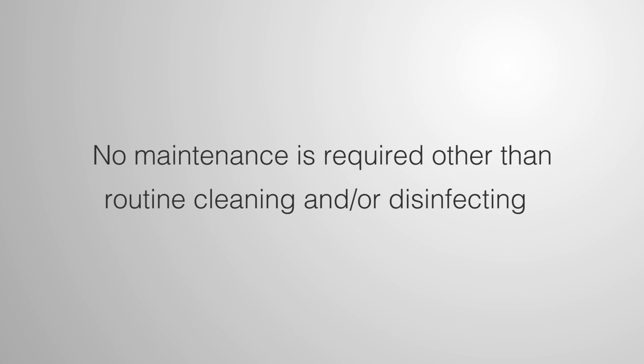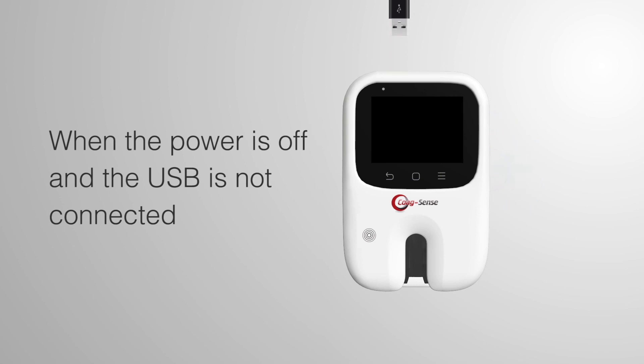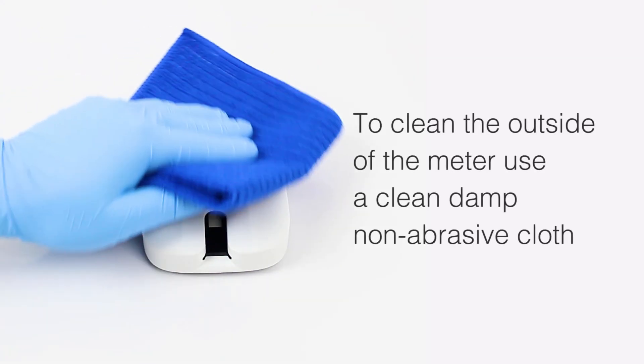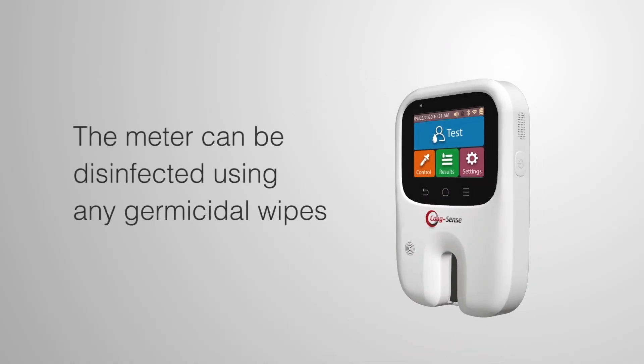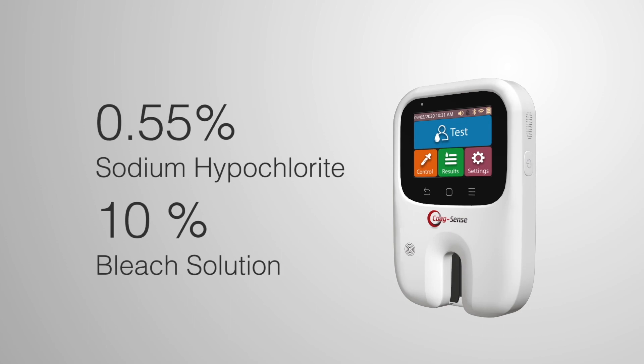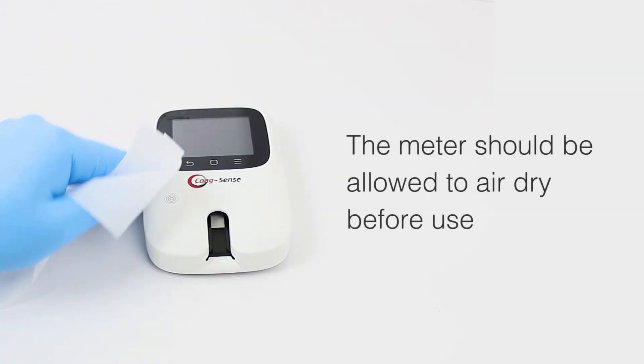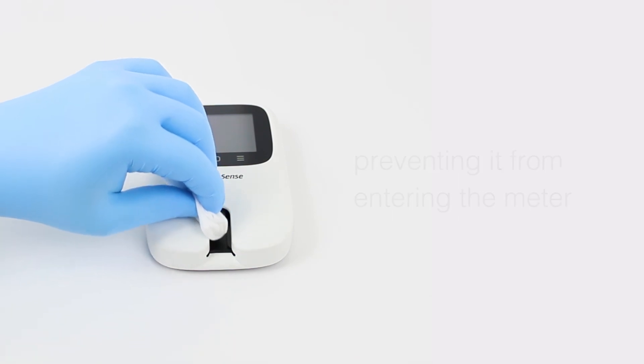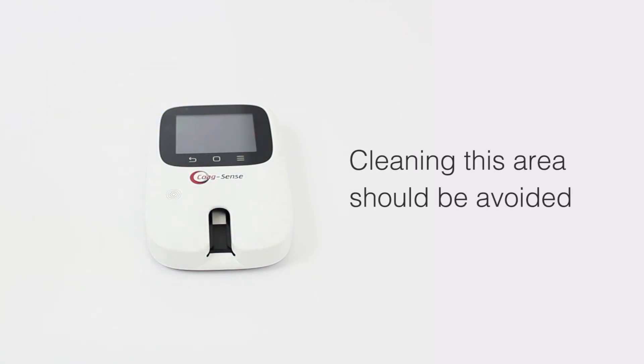No maintenance is required other than routine cleaning and/or disinfecting. When the power is off and the USB cable is not connected, the meter housing can be cleaned and disinfected. To clean the outside of the meter, use a clean, damp, non-abrasive cloth. The meter can be disinfected using germicidal wipes with 0.55% sodium hypochlorite or 10% bleach solution with a 1-minute contact time. The meter should be allowed to air dry before use. The test strip is designed to contain the patient's sample, preventing it from entering the meter. Do not clean or disinfect inside the meter where the test strip is inserted.